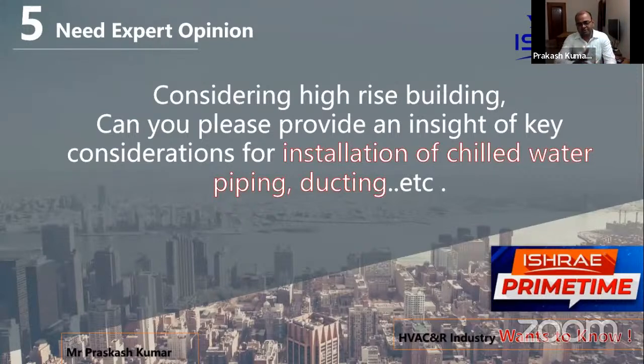Okay, no issue. Like I said previously, chilled water piping is one thing - pipe size we normally keep around 150 or 200, that's not a big problem for us. But ducting - all our ducts are used to convey air, be it fresh air, conditioned air, toilet exhaust, whatever it might be. Air travels through these ducts, so they require a lot of space. Whenever we design ducting for any AC system, we have to ensure it should be as minimal as possible. But the velocity of air inside the duct should not be too high, because at bends or edges it might start whistling. That's one consideration when we design ducting.